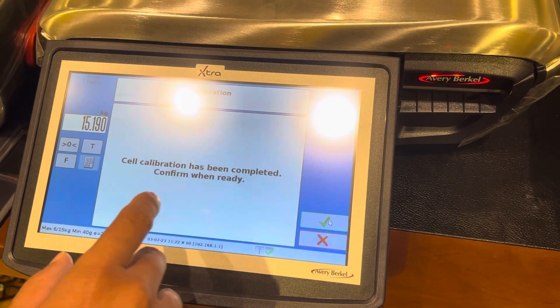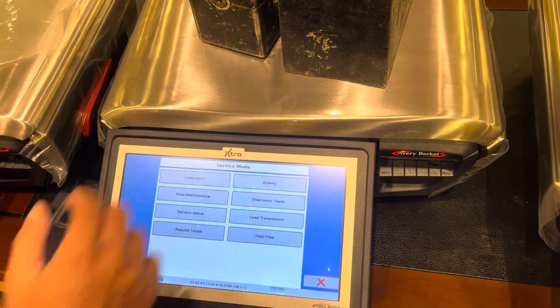It will now show: cell calibration has been completed, confirm when ready. Let's confirm. Then remove the weight.